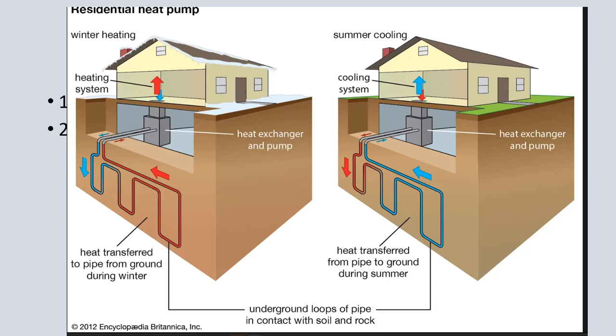It's very efficient because the water in Florida is about 72 degrees underground. So it's very easy to heat your house by extracting some heat from 72 degree water, than it is to try to extract heat from 40 degree air. Operating the other way, you can extract the cool from the 72 degree water and put it into the house. I always thought I would live next to one of the streams in Florida and just pump 72 degree water into the house for my cooling, but I never got that far in my projects. The heat pump is more efficient than an air conditioner by itself, because it exhausts some of its heat into the ground or the air.